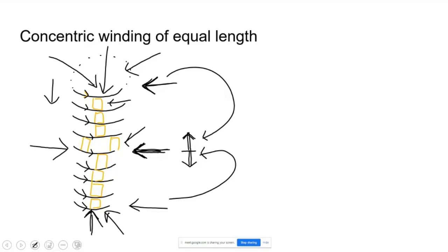I think the middle one. Yeah. The middle spacer will experience the highest stress. Then it is not the top spacer. So when we talk about electromagnetic forces, they are high on the edge or end turns.